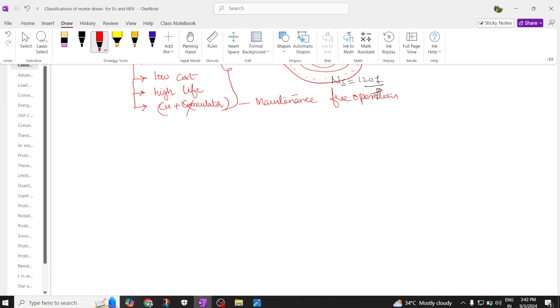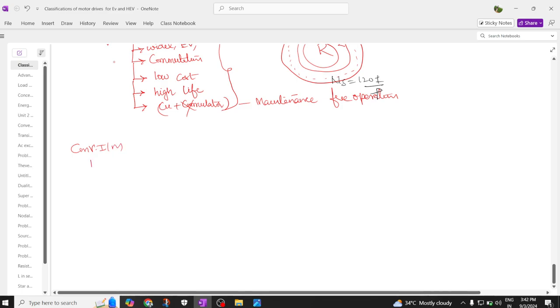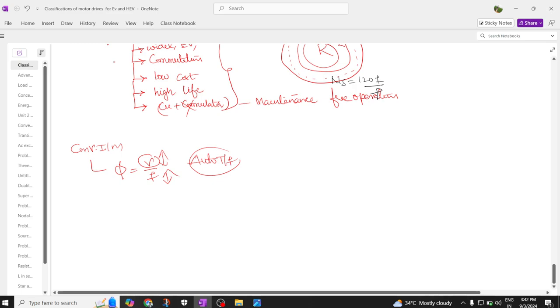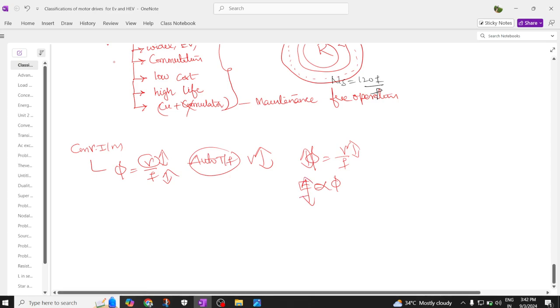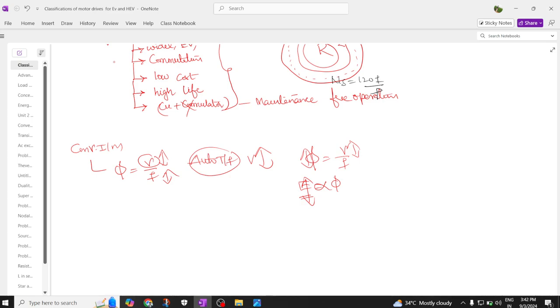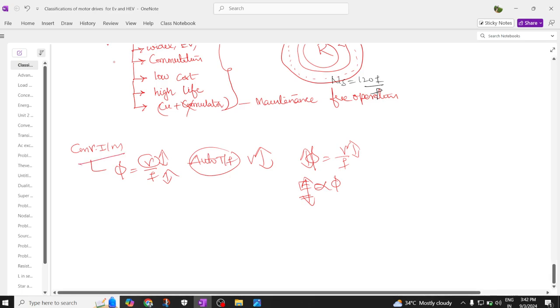The conventional method to control the speed of an induction motor uses the formula flux phi equals V by F. We can use a voltage control method as well as a frequency control method. For variable voltage, we have an auto transformer — by using an auto transformer we vary the voltage. Therefore, phi equals V by F; we are varying the voltage. The flux gets changed automatically — flux is directly proportional to EMF. The EMF also changes in the stator as well as the rotor part, and the rotor tries to catch the speed of the stator and automatically the rotor starts rotating. This is what happens in conventional induction motor speed control.